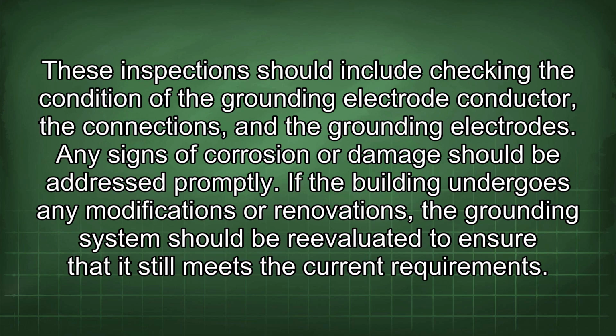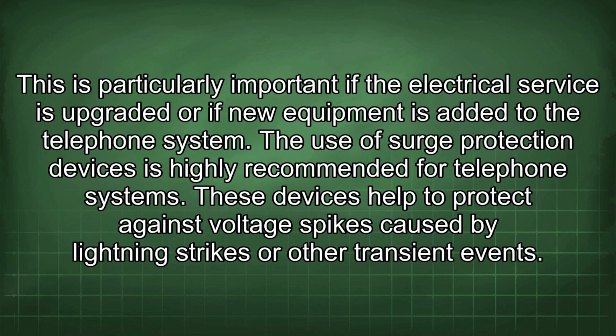If the building undergoes any modifications or renovations, the grounding system should be reevaluated to ensure that it still meets the current requirements. This is particularly important if the electrical service is upgraded or if new equipment is added to the telephone system. The use of surge protection devices is highly recommended for telephone systems.